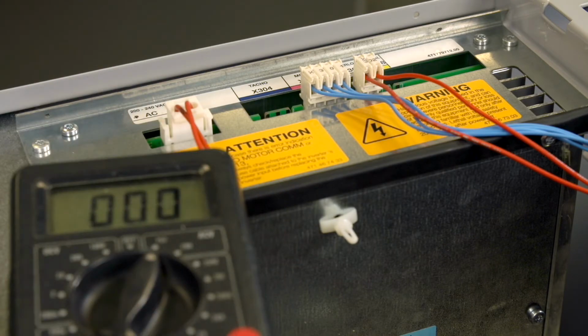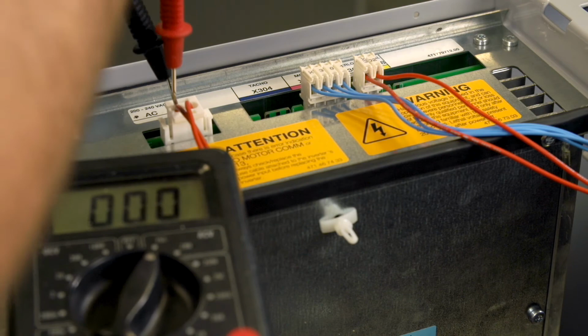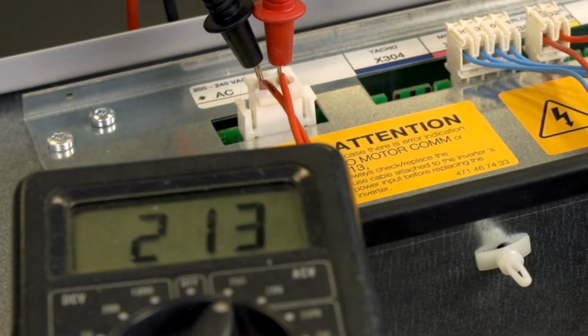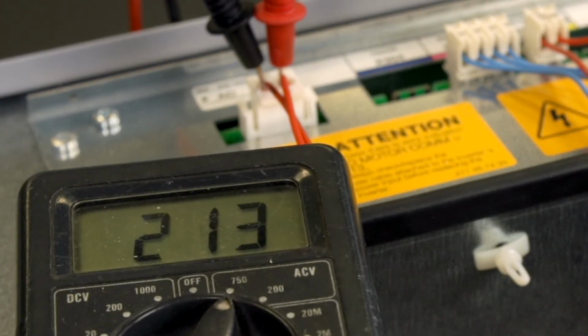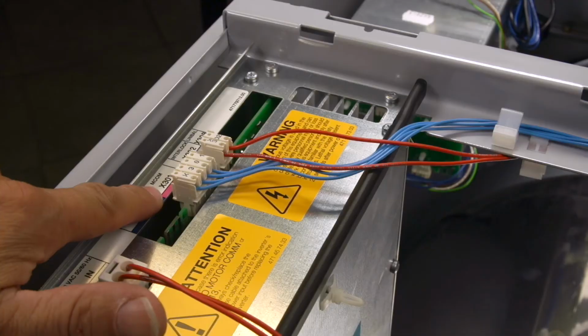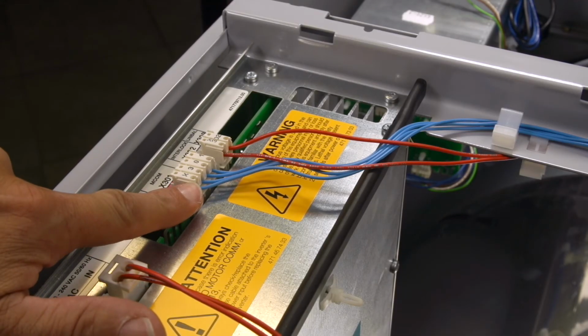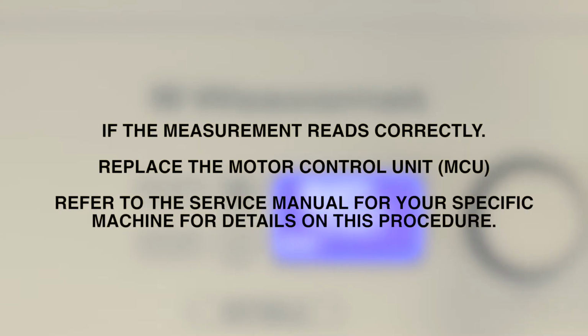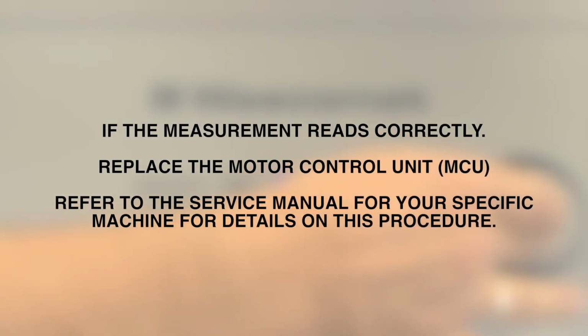Check the input voltage. It should read between 208 and 240 volts AC to the motor control unit. You should take this measurement on the rear of the connector. If the measurement reads within the acceptable range, it is likely a fault in the motor control unit communications circuits. If this is the case, replace the MCU. Please refer to the service manual for your specific machine for details on this procedure.